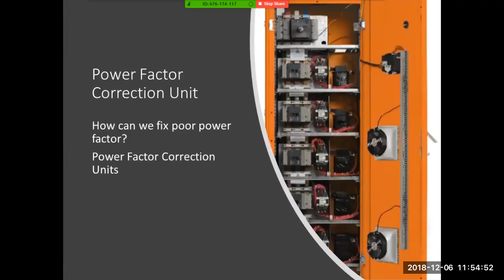Power factor is about the quality of the power. You want a power factor of 1, and that means your kilowatts and your kVA are basically identical, so you're not wasting any demand. But often wineries who have a lot of machinery, the power factor can drop quite substantially. So if you do have a power factor issue, what can you do about it? You can install power factor correction. Power factor correction is basically a bank of capacitors which corrects the quality of your power and allows you to stop wasting that demand. What it does is it removes this entire kVAR and brings the kVA down to this kilowatt value, so you've got a power factor close to 1 and you're not wasting any demand.